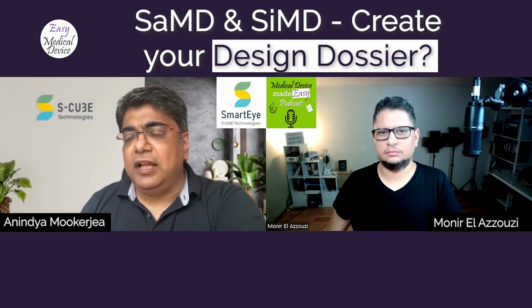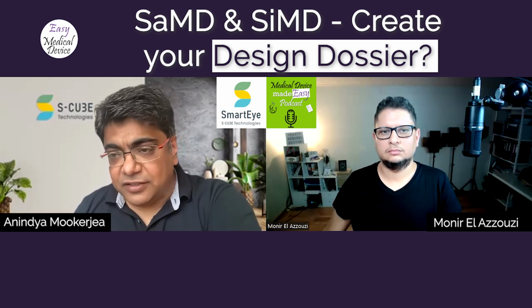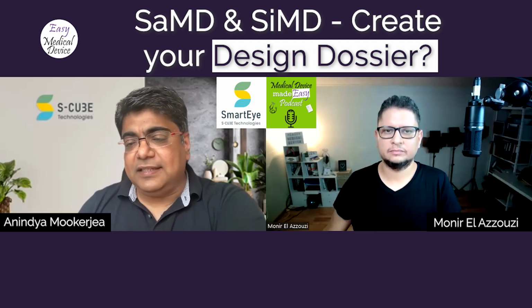Point number two, what is the safety classification? Whether it's class A, class B, or class C. Class C can do a permanent injury or death, class B an injury which is not acceptable, and class A no injury or an acceptable injury. That's the standard definition as per 62304. Now this defines your number or type of deliverables.